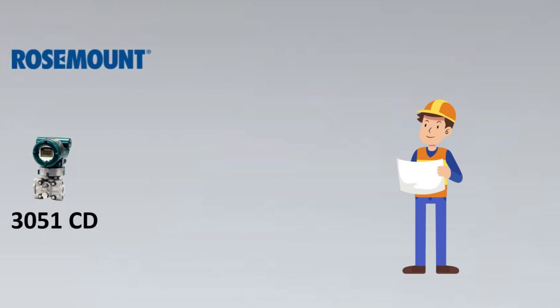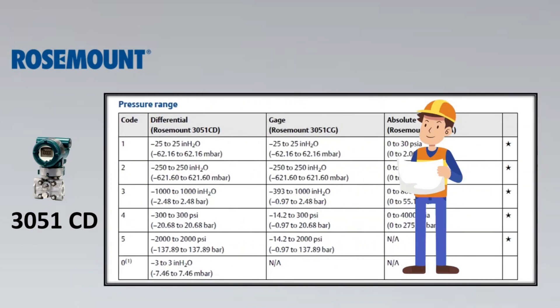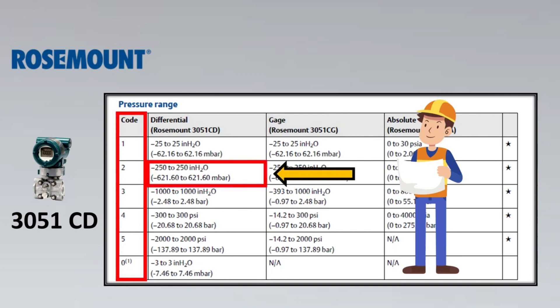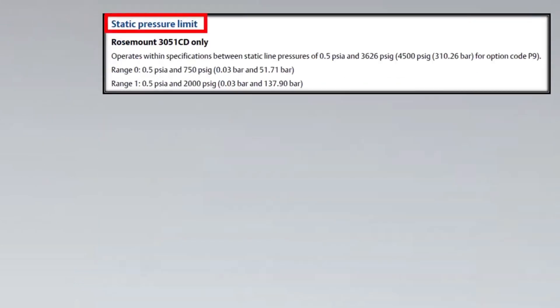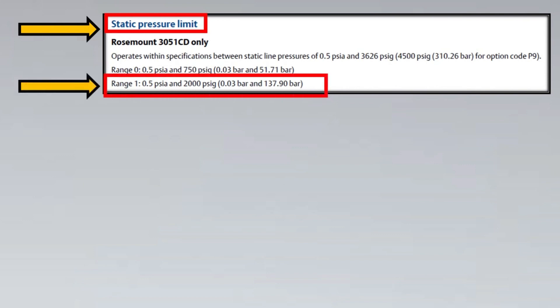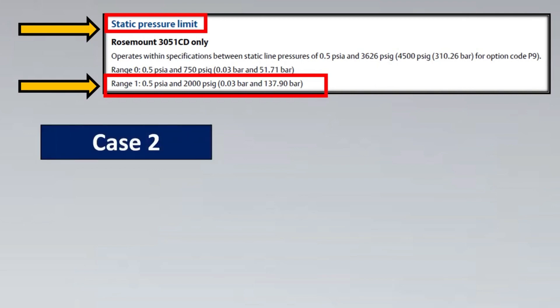Now, let's take the example of a very well-known transmitter, the Rosemount 3051CD. Other great transmitters like Yokogawa and Endress+Hauser follow the same philosophy. Looking at its catalog, there are various range codes — for a differential pressure Rosemount 3051CD, we can select any range depending upon the DP pressure range the process gives us. In the same catalog, you'll notice something called a static pressure limit.